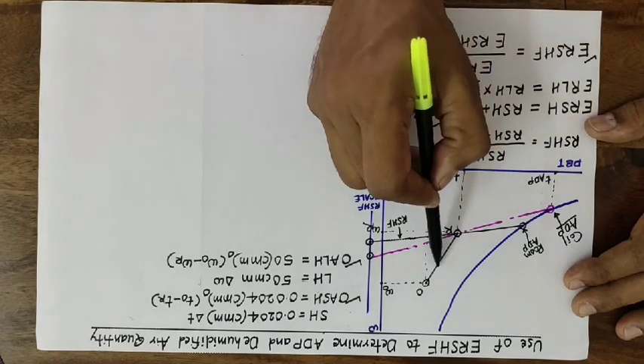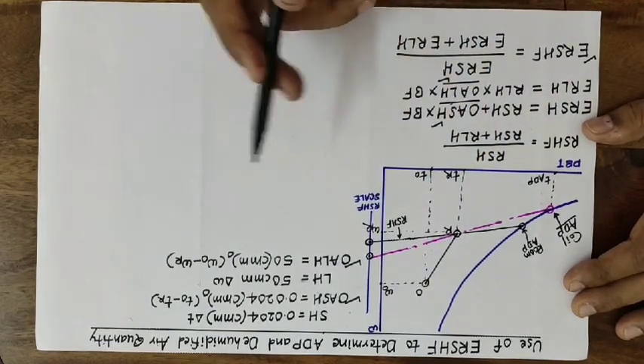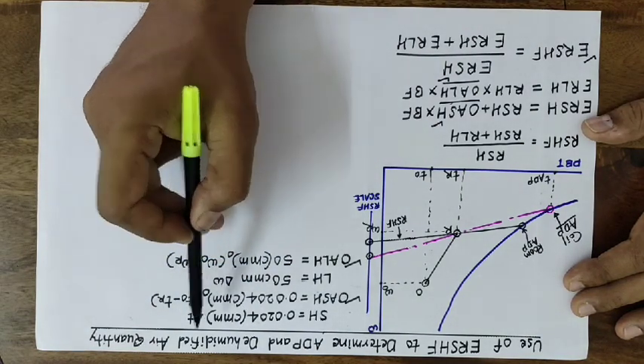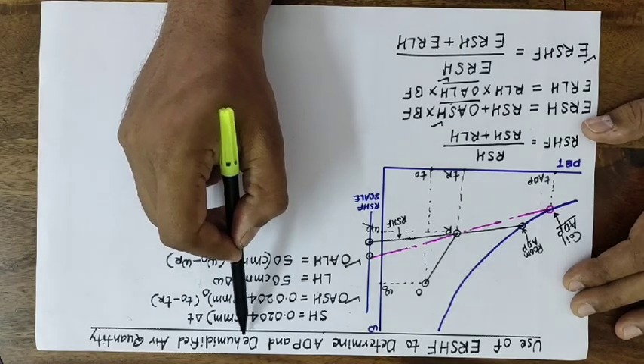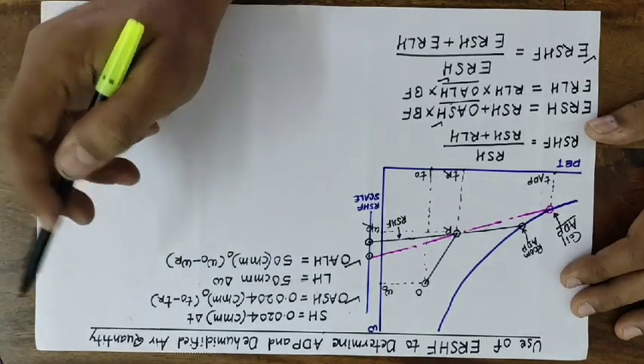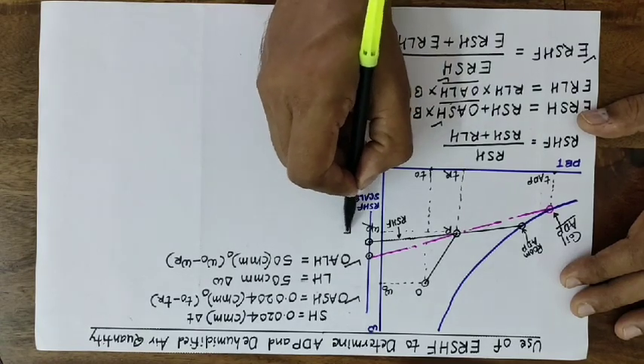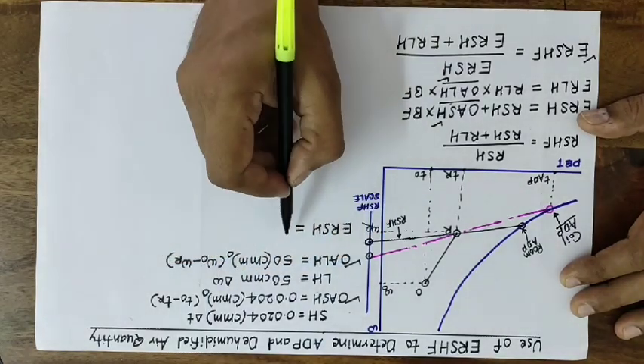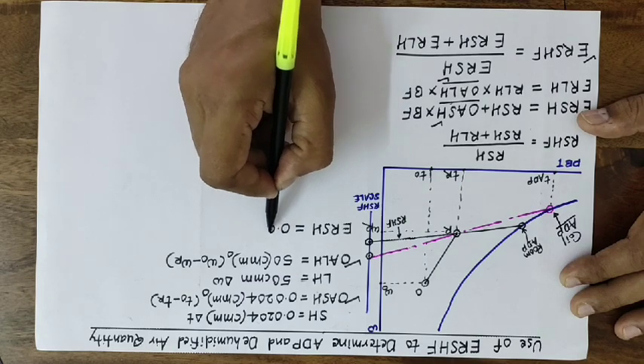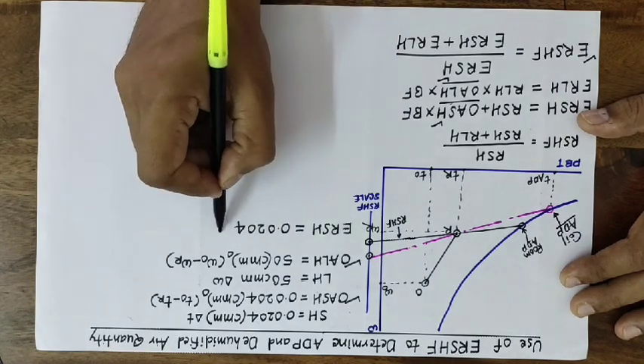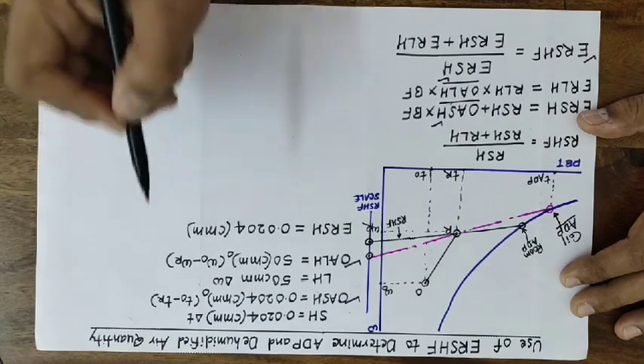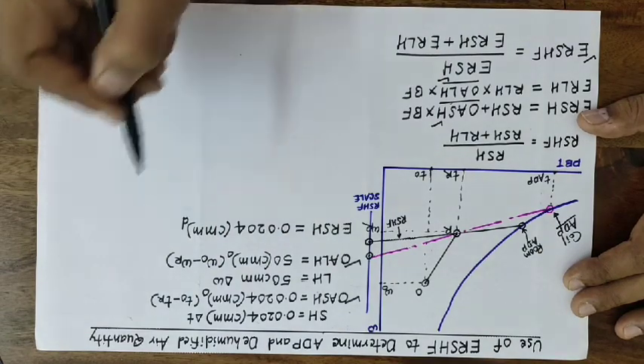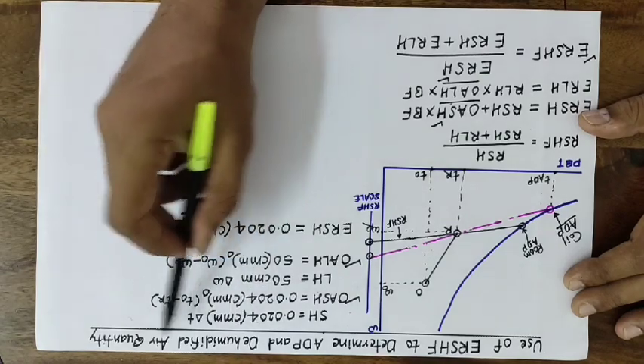Now to obtain the mixed air condition, you first calculate the total quantity of air supplied to the room — also called the dehumidified air quantity. For this, you can write the effective room sensible heat formula using the same basic formula: ERSH = 0.0204 × CMM_D × ΔT, where the suffix D denotes dehumidified air quantity.